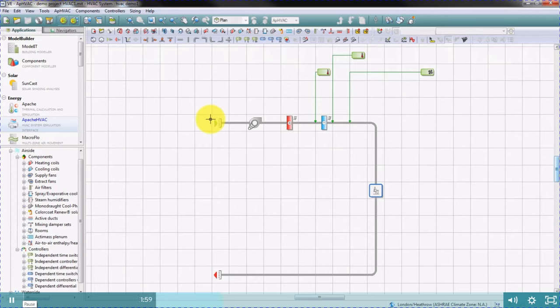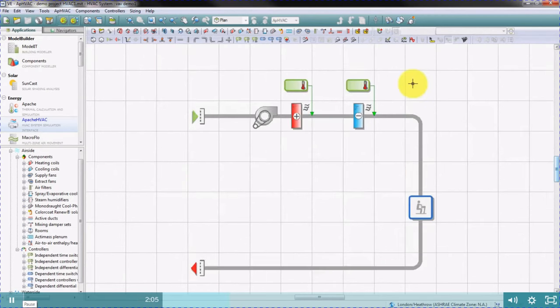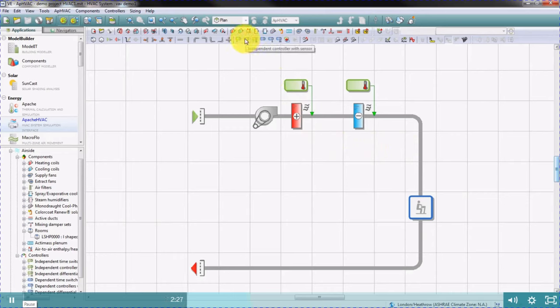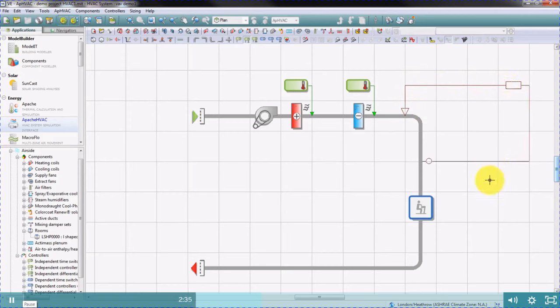Next, we're going to look at an example of a controller with a sensor. Let's open up a different network. Here we have a partially completed example of two coils supplying air at a fixed temperature into a space. We're going to place a control to vary the flow rate to keep the room to a desired set point. To do this, we're going to use an independent controller with a sensor. Click once to define the control point, the second click to define the control box symbol, and the final click to define the sensor position.